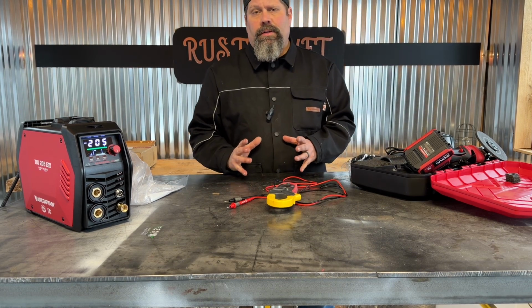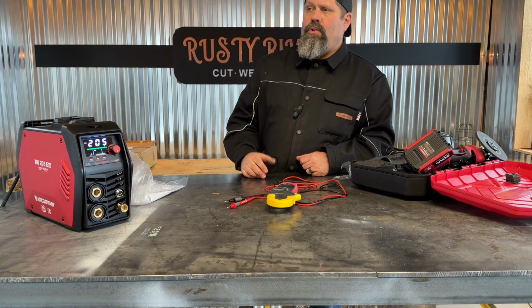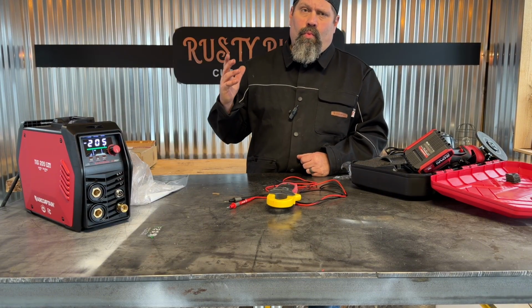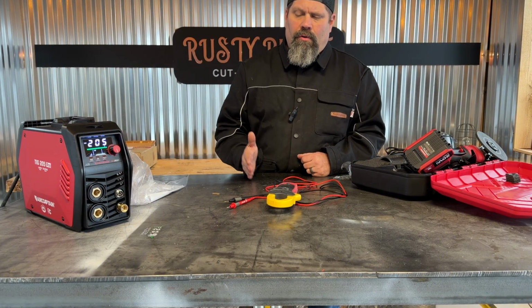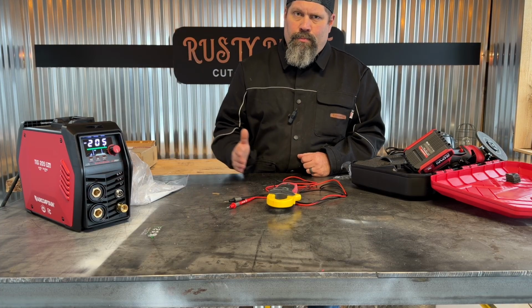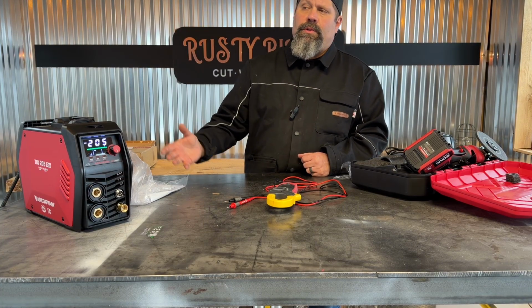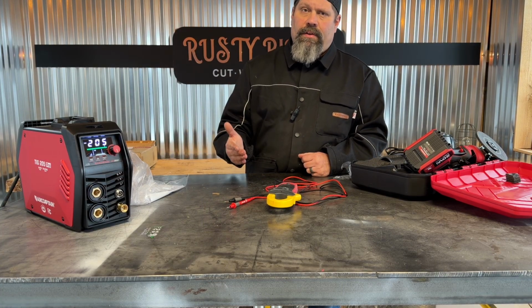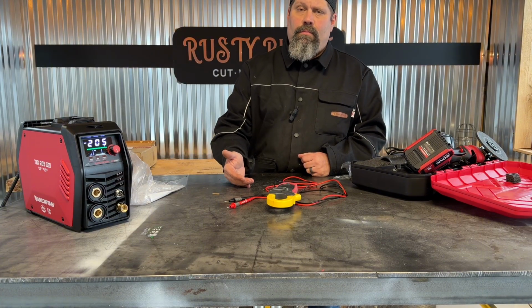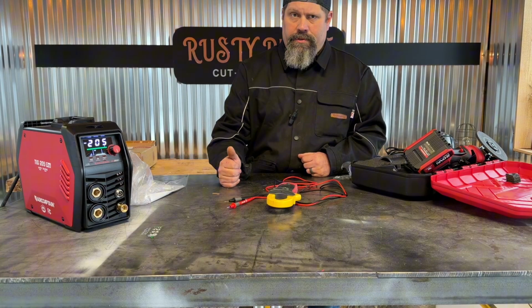One thing you don't want to do is run your welder on a weak generator. You want to go overboard with that generator, much more power than you need, because when you dip down on current and it starts revving, you're going to get voltage spikes and more harmonic distortion.